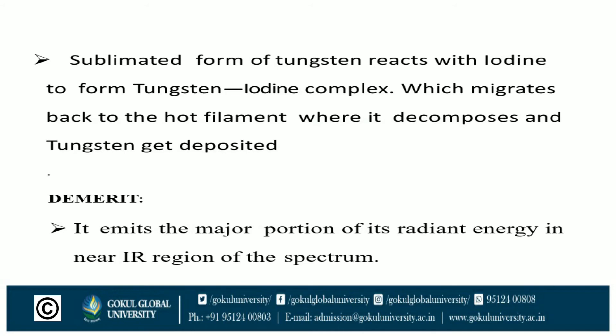The sublimated tungsten reacts with iodine to form a tungsten-iodine complex, which migrates back to the hot filament where it decomposes and tungsten gets re-deposited. The demerit of this lamp is that it emits the major portion of its radiant energy in the near-infrared region of the spectrum.